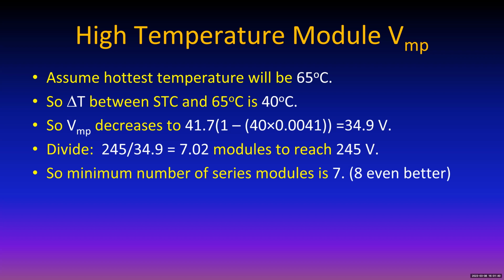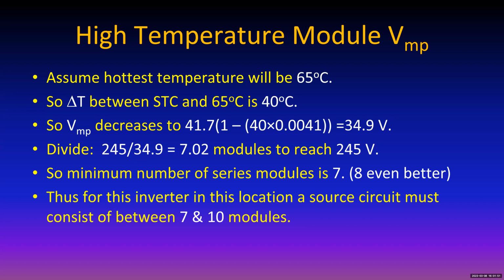7.02, that's pretty close to 7, and it's not going to give you a problem very often. If you really press for space, you could do 7 as a minimum, but 8 would be a better number. Somewhere between 7 and 10 would be the number of modules in a circuit. So it's not that big of a range: 7, 8, 9, 10. There's only 4 choices of how long your strings can be.